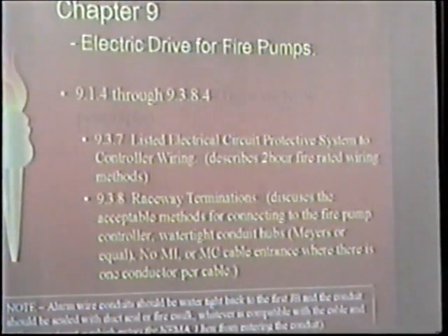Raceway terminations, that's what we were talking about. MI, MC cable, any of those 2-hour rated systems should be terminated outside of the controller and then converted back to standard wire.